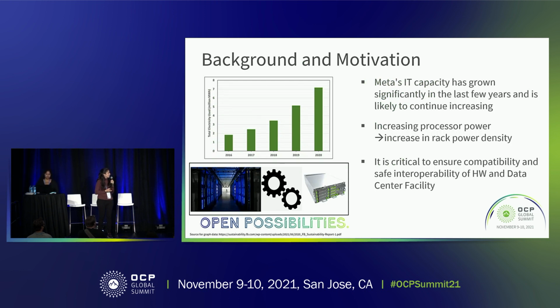Some background here. As you can see in the graph on the top left corner, Meta's IT capacity deployment has increased significantly in the last 5 years. And it is also projected to go on increasing in the future. This increasing power demand, and in parallel, the processor power, has also gone on increasing in the last few years and is projected to continue the same trend. So when we put these two things together, it basically means that to support the higher power that we are anticipating, we would have higher power racks in our data centers.